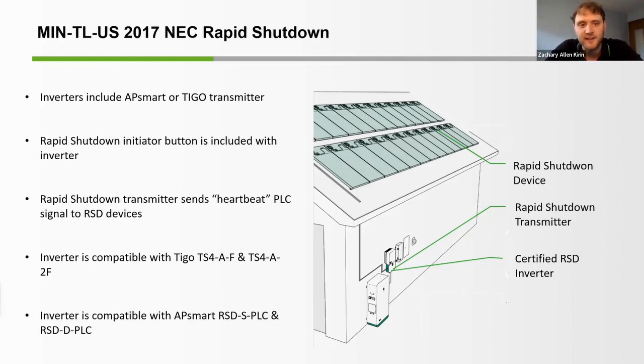We all know how the rapid shutdown transmitter works. It features the heartbeat signal, and that is implemented onto the DC lines of the array. The rapid shutdown solution will pick up the heartbeat signal and continue normal operation until that heartbeat signal is no longer present, in which case the TIGO or the AP Smart rapid shutdown device will stop sending the voltage down to the inverter.